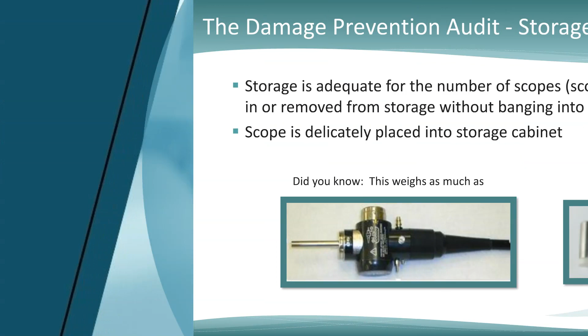Another mistake we see facilities making is not having adequate storage for the number of scopes they have. So what that means is that scopes can be placed in or then removed from the storage without banging into other scopes. That light guide connector that's hanging off of most scopes, particularly large diameter Olympus scopes, that light guide connector weighs as much as an ortho mallet. And it hangs just perfectly lined up to hit that distal tip where everything is so expensive to repair. And so if you find that technicians have to kind of move scopes out of the way, or even if they're just very quickly putting scopes in, sometimes that light guide connector will then begin swinging around. And I promise you, everybody knows you do not want an ortho mallet swinging around inside your flexible scope storage cabinet. But you already do have an ortho mallet swinging around inside your storage cabinet. It's the light guide connector.